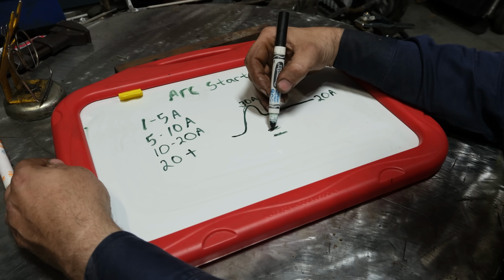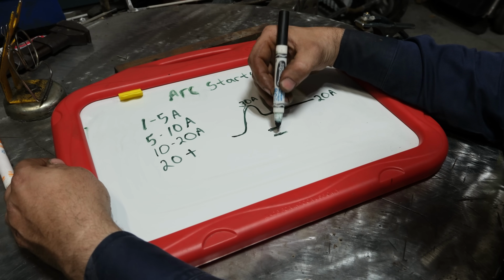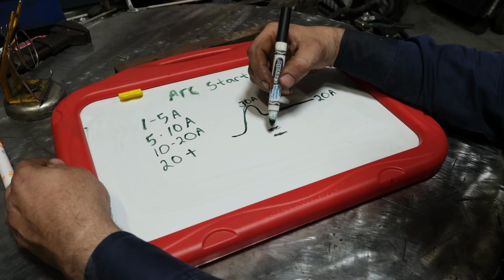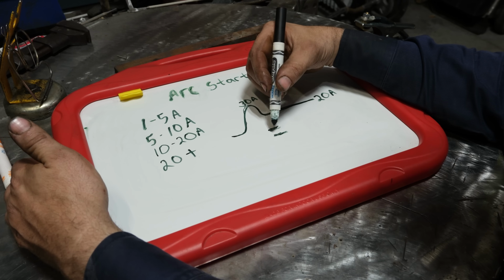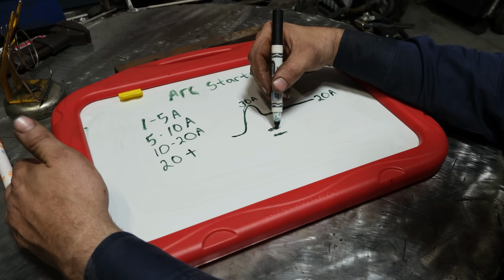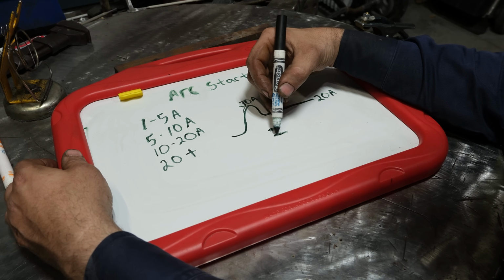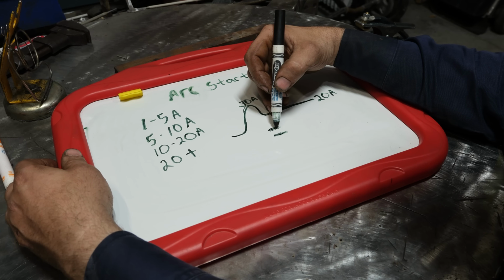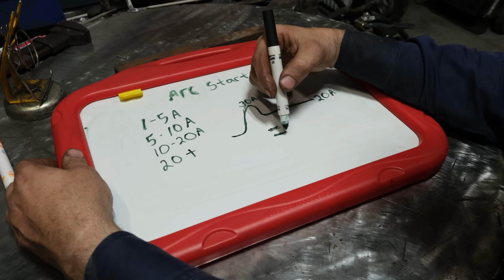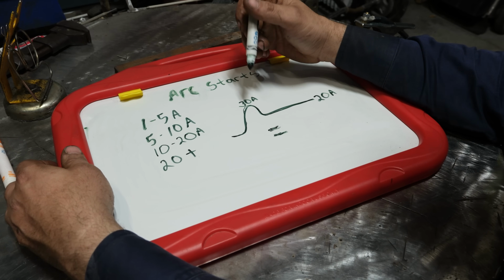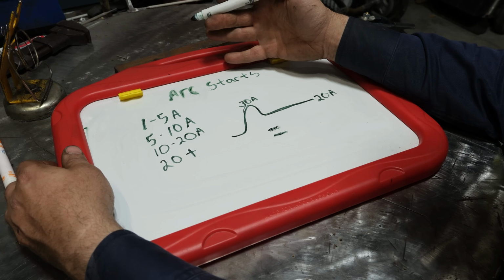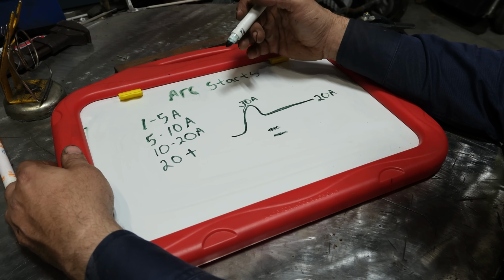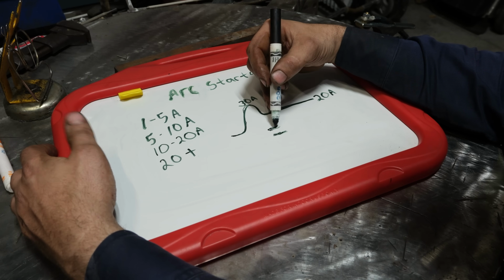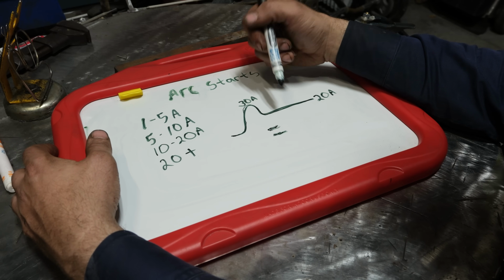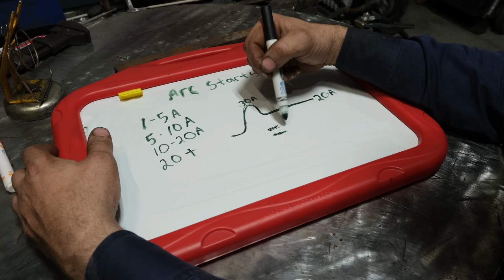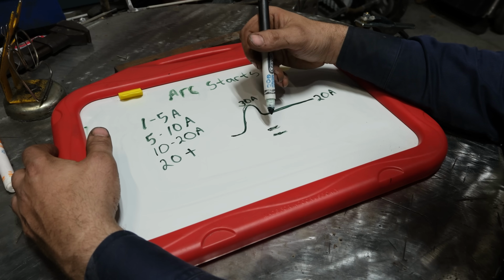Well, those older machines over time will get erosion where the points start to erode, the gap, maybe the machine was bumped too many times or just wore, the gap gets too large, and dust and material will often build up on it, which all affects the voltage that's required to cross the arc gap in them. So with your older machines, it's very common to have to routinely, aka once a year, take some emery cloth, polish the surfaces, take a set of feeler gauges, and gauge the gap on them to get it within spec.